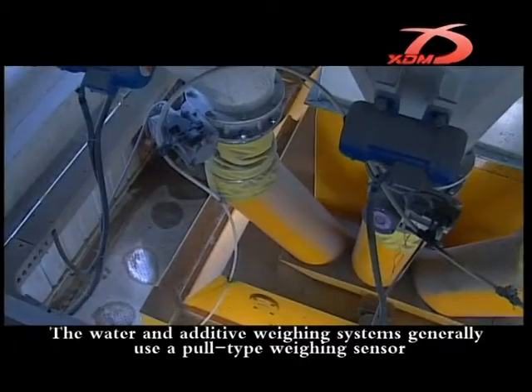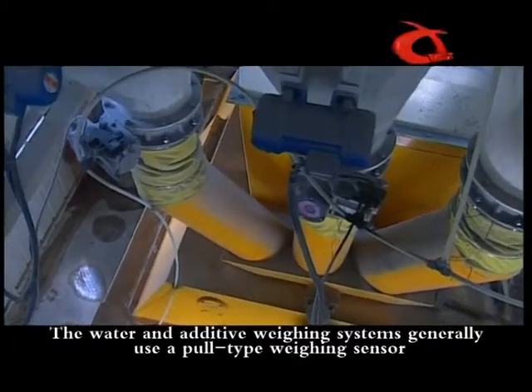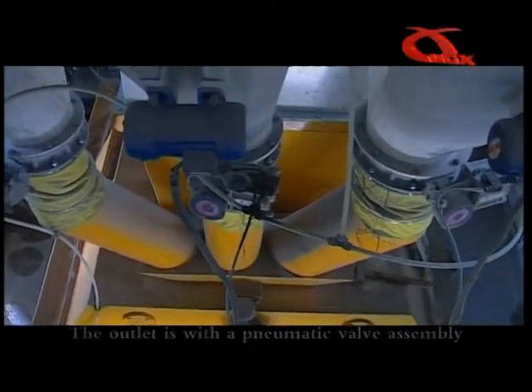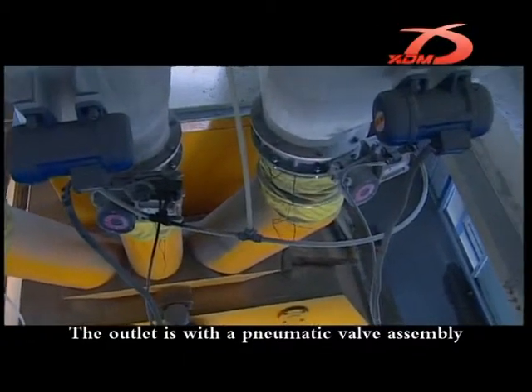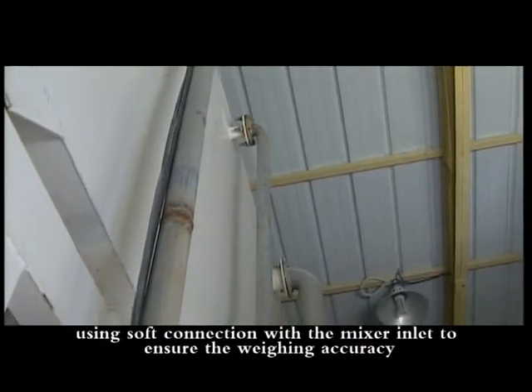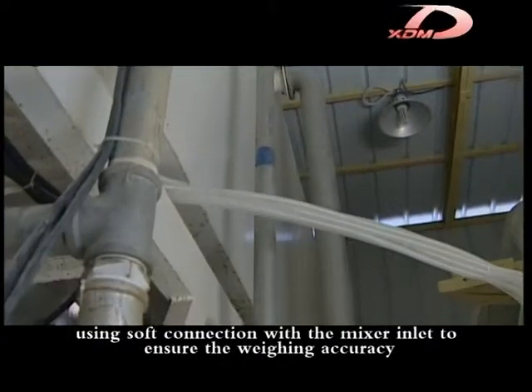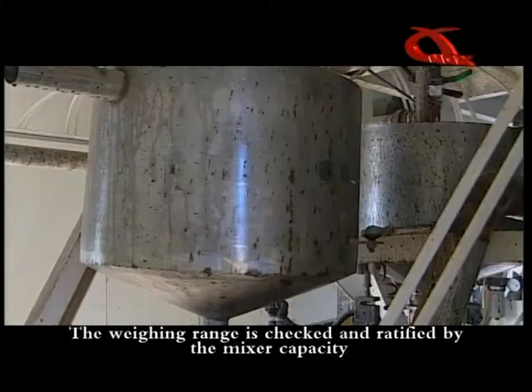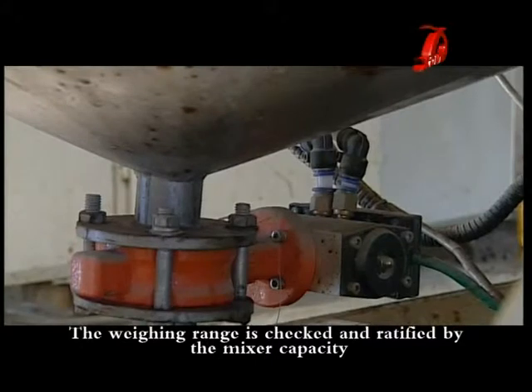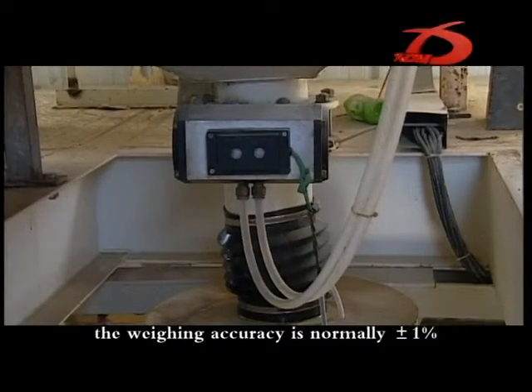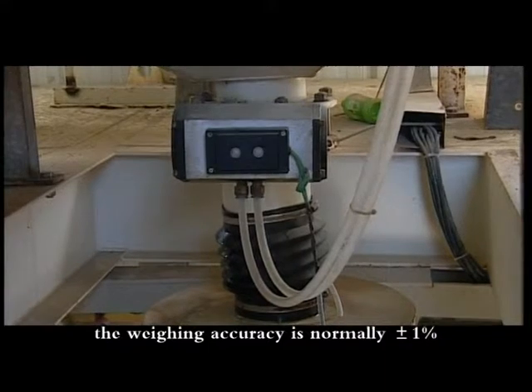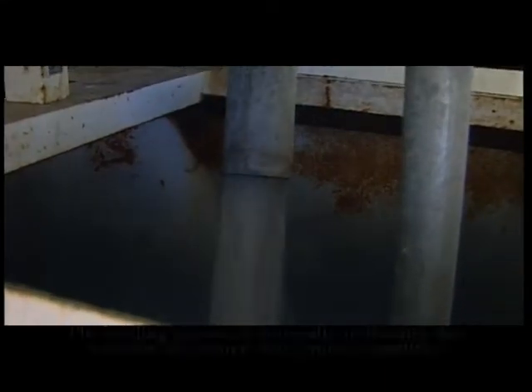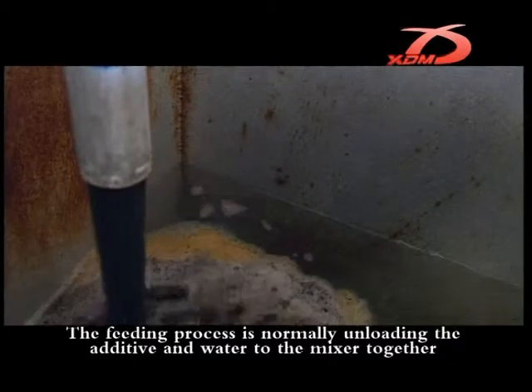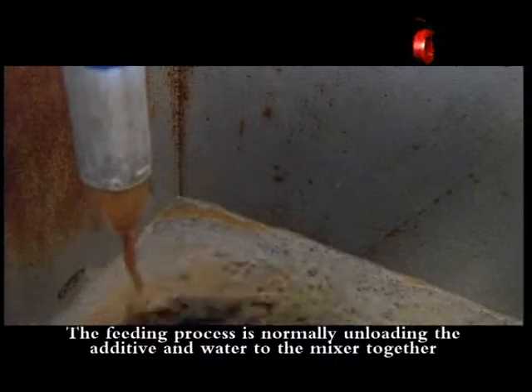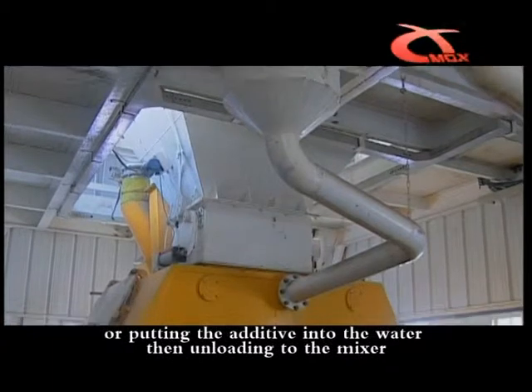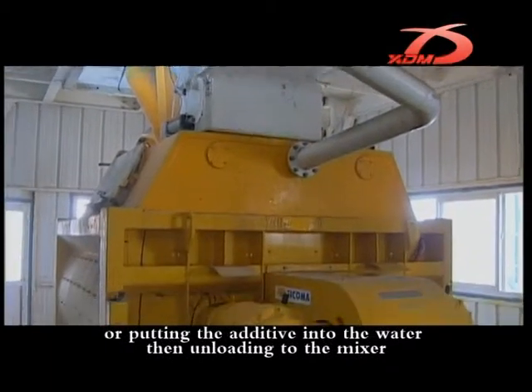The water and additive weighing systems generally use a pull-type weighing sensor. The outlet is with a pneumatic valve assembly, using soft connection with the mixer inlet to ensure the weighing accuracy. The weighing range is checked and ratified by the mixer capacity. The weighing accuracy is normally of plus or minus 1% error. The feeding process is normally unloading the additive and water to the mixer together, or putting the additive into the water, then unloading to the mixer.